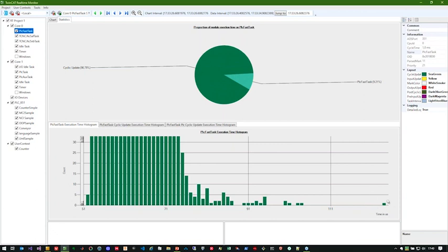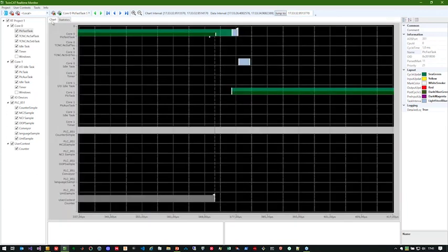But I would like to see exactly when this happens, because this could be the reason for a cycle time exceeding. If we have a look at this timestamp and I click on this, then the timestamp should change to the latest cycle in which this cycle time occurs. Then I press jump to and switch back to the chart, and I'm exactly at the location where the cycle time exceeding or whatever occurs. So that's how you can do analysis.